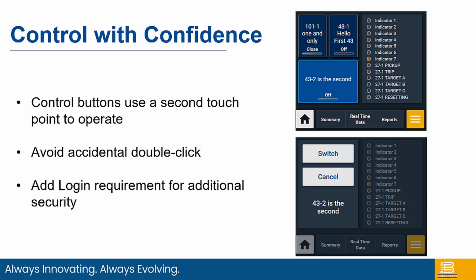In addition, let's say a user is appropriate to do control functions. Somebody might be concerned that if they tap accidentally twice, it might perform an operation accidentally. So we have two-point operation. Every time you press a button, the select button will be in one location of your physical touch, and the second button, the operate, will be in a different spot. So no matter where that button is, it's going to move the operate to a different place. Doesn't seem like a big thing, but if anybody's accidentally double-clicked something, sometimes it does cause an issue.